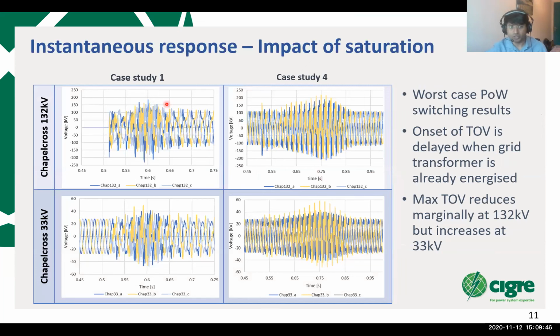When we do not have the saturation considered, the temporary overvoltage observed here appears much quicker, whereas when we have saturation considered, that gets delayed by quite a lot. And in case of 132 kV, the peak voltage observed in this case is slightly lower than what is observed in case 1. But in case of 33 kV, it increases marginally.